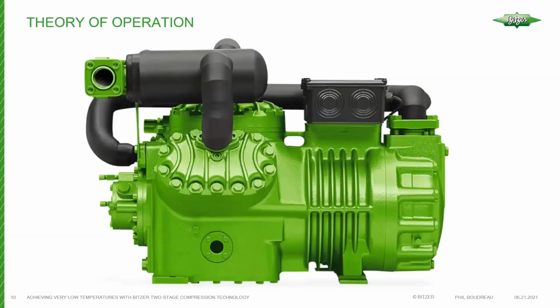So let's talk about the theory of operation of the two-stage compressor. We have a suction manifold. For a 6-cylinder compressor, the top head and the right-hand side head, if you're looking at the oil pump end of the compressor, are coupled together via a suction manifold. The suction manifold has a screen inside, a suction screen, basically a long cylindrical screen that sits inside that chamber.